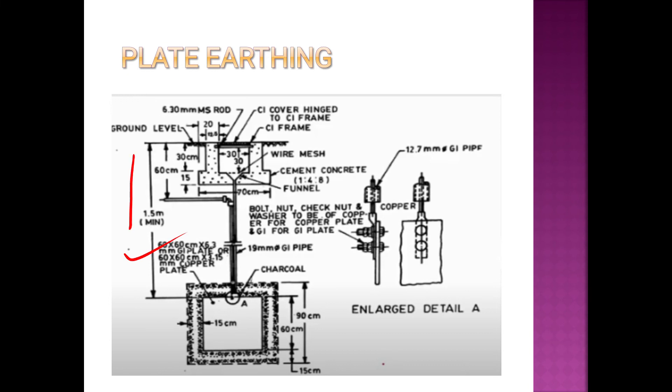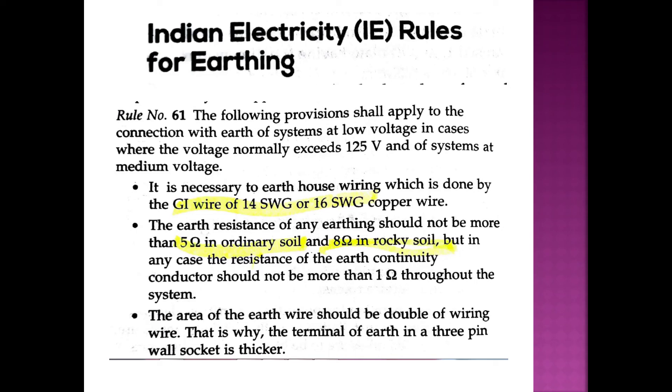The pipe is buried 60 cm deep and 1.5 m from the ground. We fill it with charcoal and sand. Per IE rules: voltage normally exceeds 125 volts in medium voltage conditions. House wiring uses GI wire of 14 SWG or 16 SWG copper wire. SWG stands for Standard Wire Gauge.